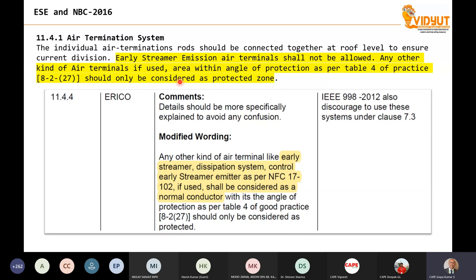But once the draft is published for public comments, anybody can comment. As a result, there were thousands of comments, and specifically regarding this particular subject, this document is available. You can download it and see it. One of the largest ESE manufacturers in the world, I'm sorry, you can read the company name, made a comment. The detail which I have highlighted in the previous one should be more specifically explained to avoid any confusion. And what they recommended is a modified wording: any other kind of air terminal like early streamer emission, dissipation system, controlled early streamer emitter as per NFC 17102, if used, shall be considered as a normal conductor.